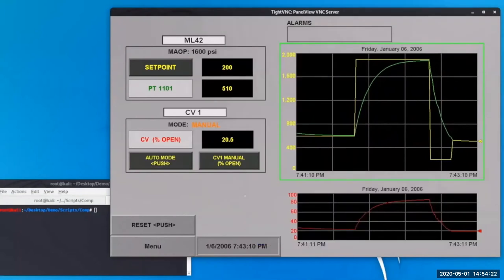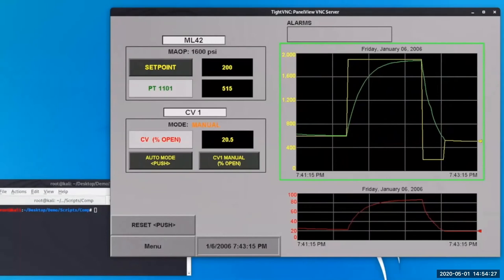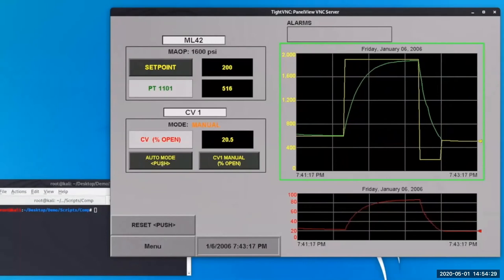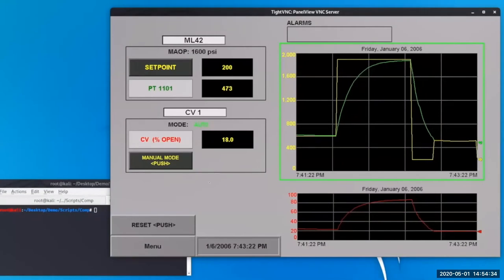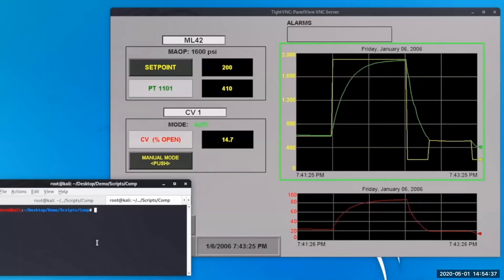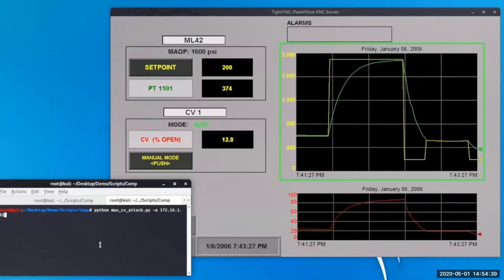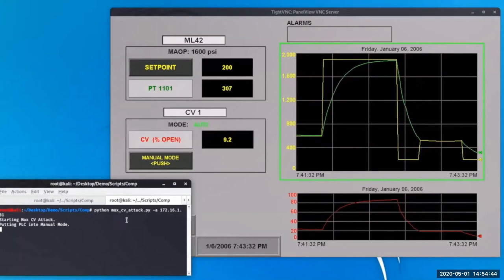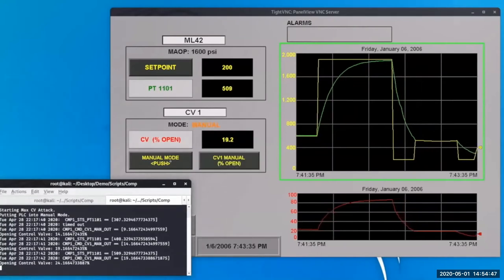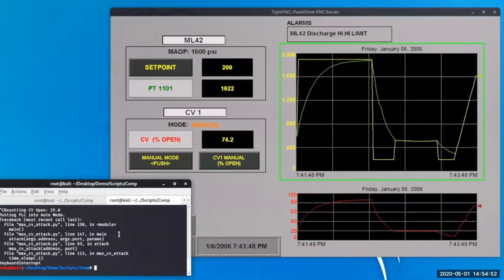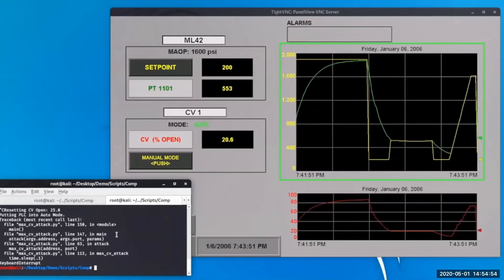Entering that value sends the tags down to the controller. There are actually two tags sent to the controller in this situation: the percentage open, and the manual/auto mode flag. So if we wanted to automate this through a bypass attack, we would essentially need to directly write values to the controller and manipulate the same actions — setting the manual tag and the percentage we want the control valve opened by.